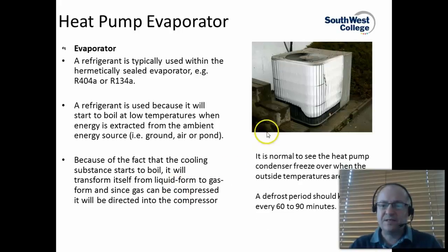So sometimes it's normal to see heat pumps freeze over when the outside temperature is very low. You can see they actually frost up. So here's an air source heat pump that's frosted up on the outside. But a defrost function is typically built into the control system of a heat pump that will defrost the evaporator on a regular 60 to 90 minute cycle.